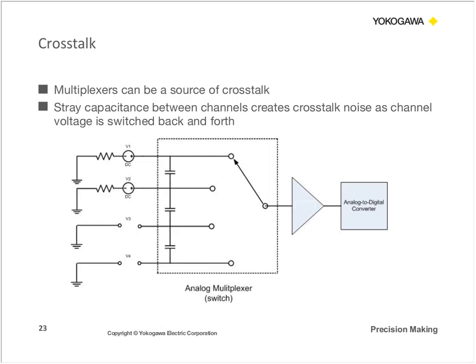And what happens is the multiplexer's inputs have a capacitance that stores a certain amount of voltage charge, and that's directly related to the impedance at each signal source. So it takes some time for the voltage to really bleed off, and if you're dealing in situations where you have high frequency signals and you need to switch quickly from one channel to the other, there might not be enough time to bleed off the voltage and drop it back down to zero.